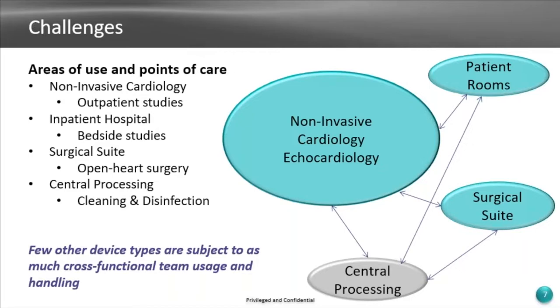This is a tip protector. We have them made, but you can get them from Civco, the company I usually recommend for consumables. A tip protector should be on a TE probe anytime that probe is not being processed or in use. Always—that's just a rule of thumb.